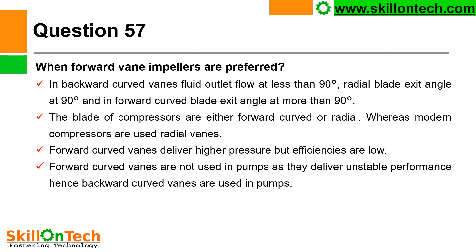Question 57: When are forward vane impellers preferred? In backward curved vanes, fluid exits at less than 90 degrees; radial blades exit at 90 degrees; and forward curved blades exit at more than 90 degrees. The blades of compressors are either forward curved or radial, while modern compressors use radial vanes. Forward curved vanes deliver high pressure but efficiencies are low. Forward curved vanes are not used in pumps as they deliver unstable performance; hence backward curved vanes are used in pumps.